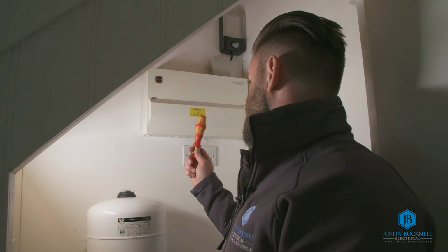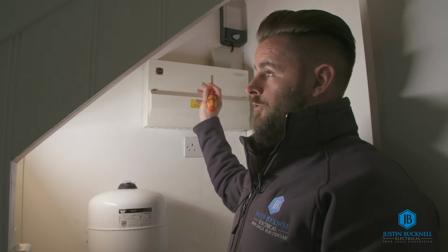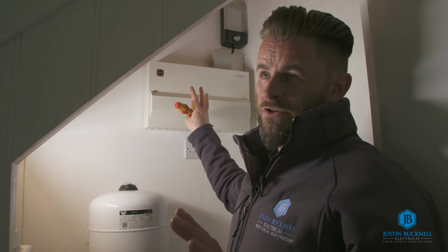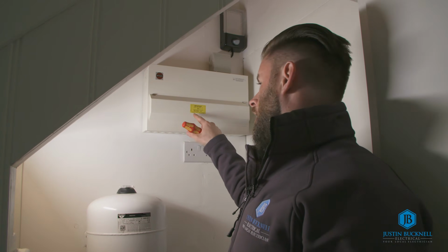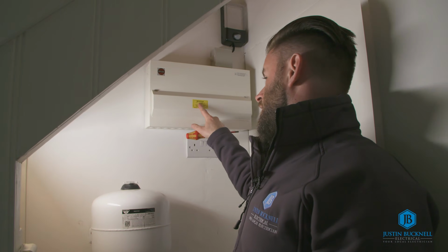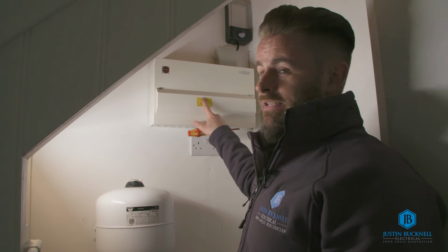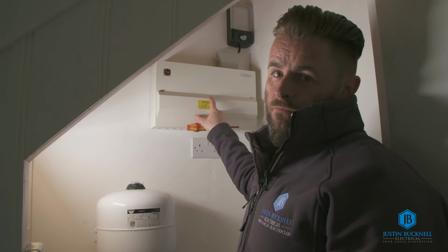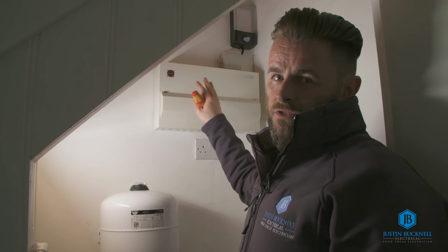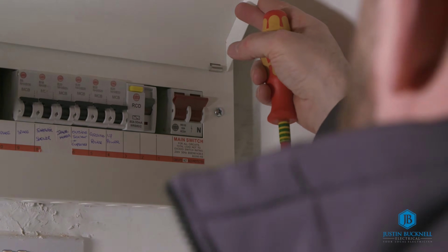A few other observations that we can see from this consumer unit is that there is absolutely no inspection sticker on here at all. It's quite a new installation, it's been done in the last year. There's even a manufacturer's sticker on here which asks for the tightness of all the factory connections to be checked, and then this label removed. So that's not even been removed, so that just makes me feel a bit uneasy about some of the other stuff that we've seen already. So we're going to take this cover off and have a look inside.